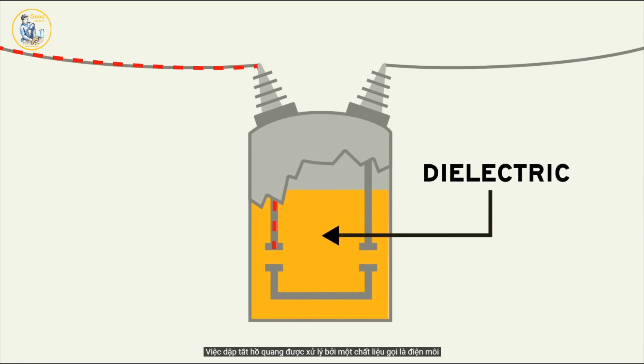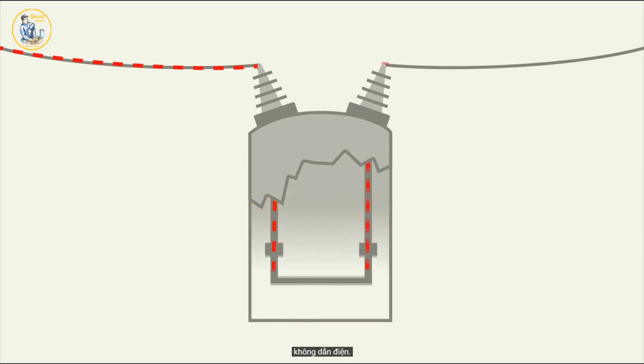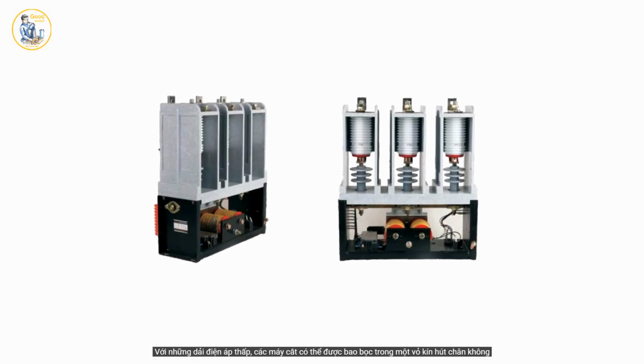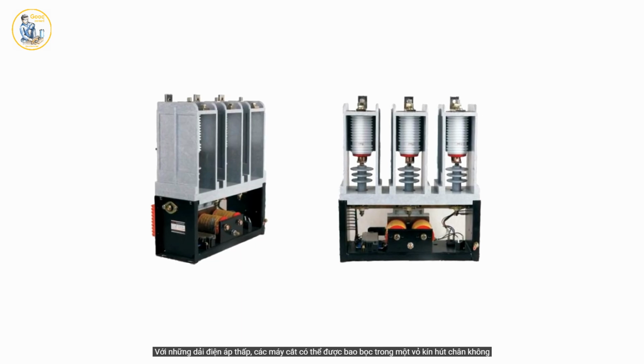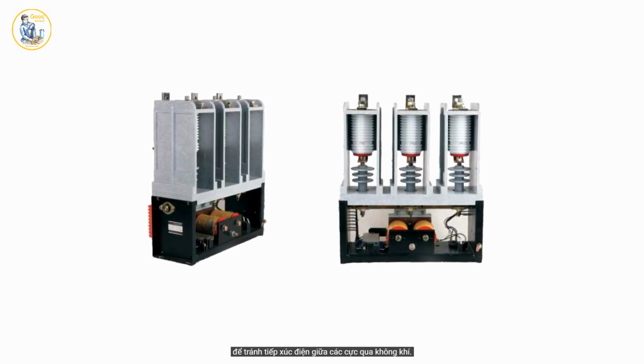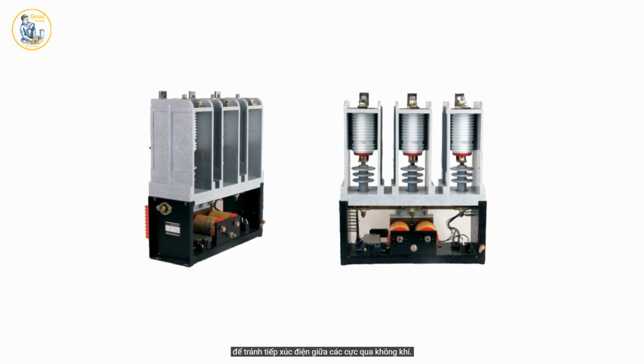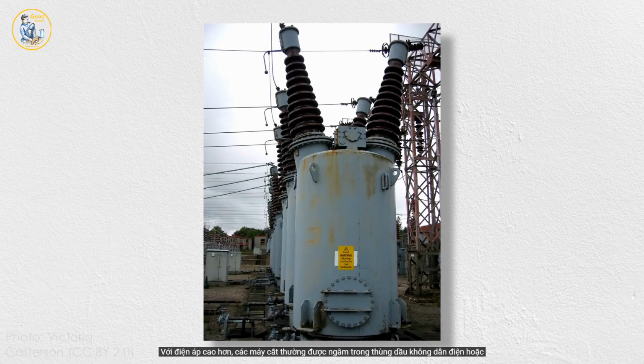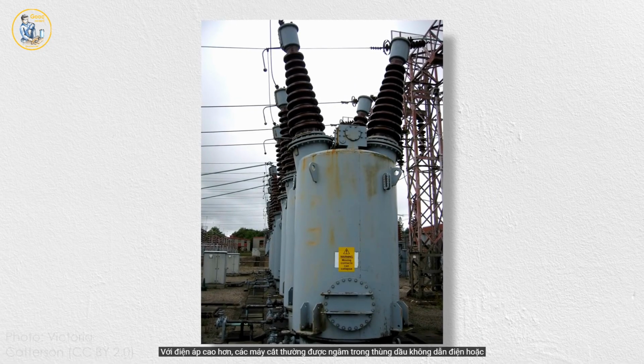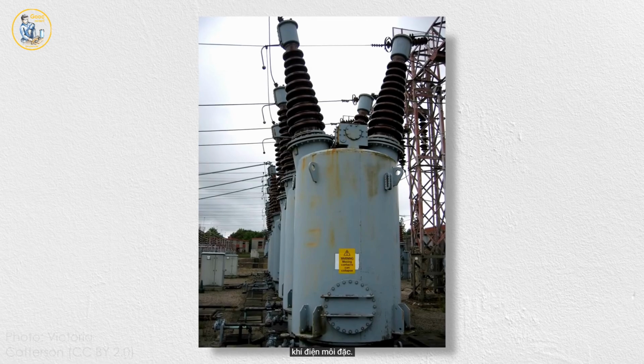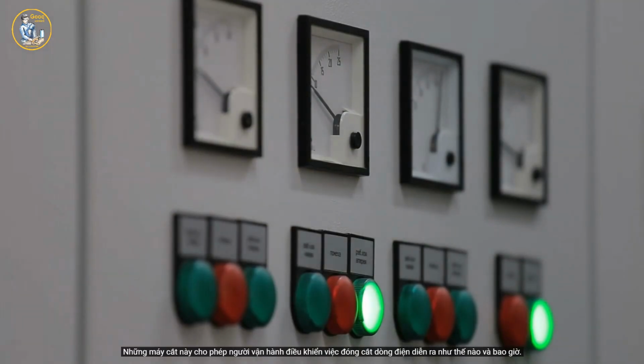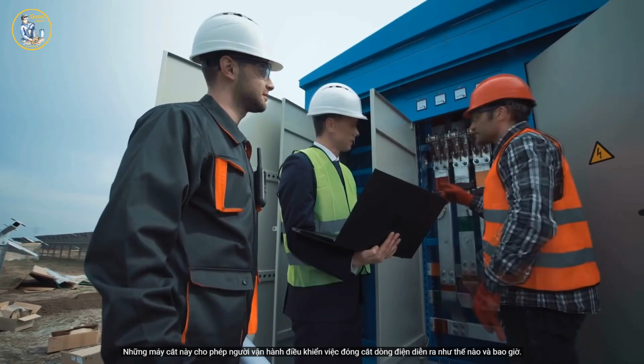Extinguishing the arc is accomplished by a material called dielectric that doesn't conduct electricity. For lower voltages, the circuit breakers can be located in a sealed container under vacuum to avoid electricity conducting in the air between the contacts. For higher voltage, breakers are often submerged in tanks filled with non-conductive oil or dense dielectric gas. These breakers give grid operators more control about how and when current gets interrupted.